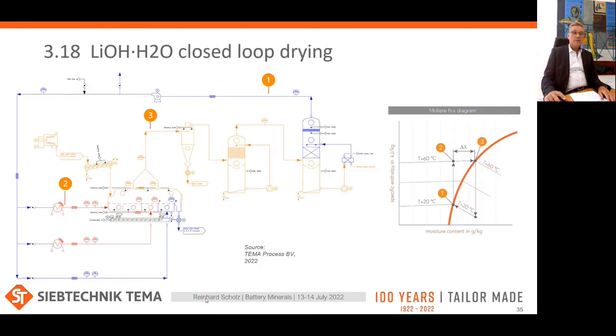In order to avoid direct contact with CO2 from the air, the CO2 can be removed from the air or other gas media can be used. In most cases, however, a closed-loop drying process is applied. This process is explained on the left here, the simplified P&ID. On the right, the same process is depicted in an HX diagram. I'm starting here with point 1, the coldest point in the process. Here in the diagram.